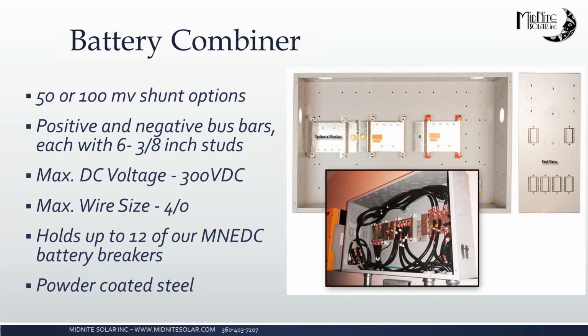It's a good idea, just like in the PV modules, when we go over 2 strings, to start putting overcurrent protection on each string. It's the same in the battery world. So that makes a convenient place to do that. Or feeding, say, like 4 Sunny Islands, you could put the battery breakers in here. And they are all powder-coated steel.